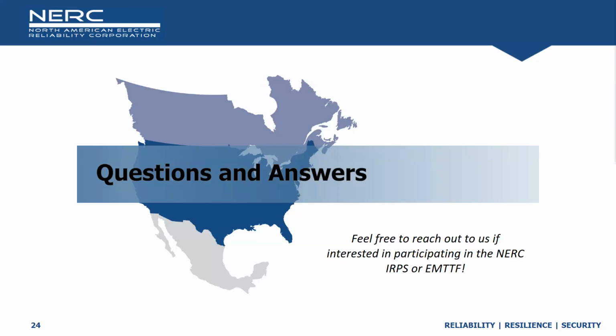Yeah, and we may have talked about that in the other interconnection process webinar, but the idea is that the NERC standards are the minimum, right? Where regions may have, like you just said, special needs. So what we would expect in that situation is you take the NERC standard, take PRC-024, I know those have regional variants, but that's maybe a good example. PRC-024 has some requirements for the continent, but they have some locational ride-through differences for those different systems' needs.